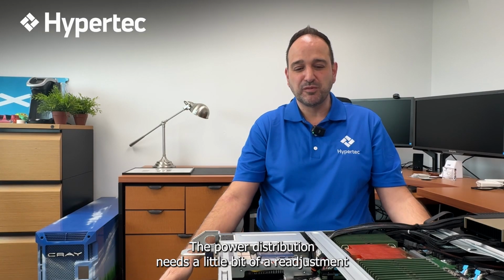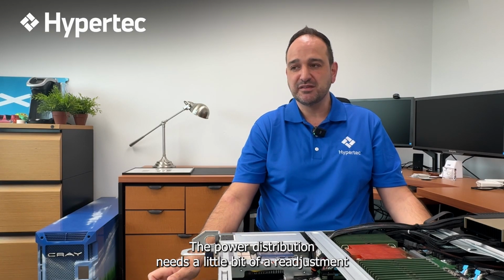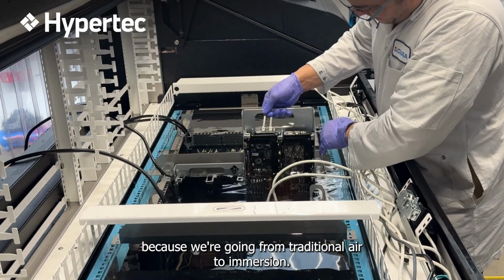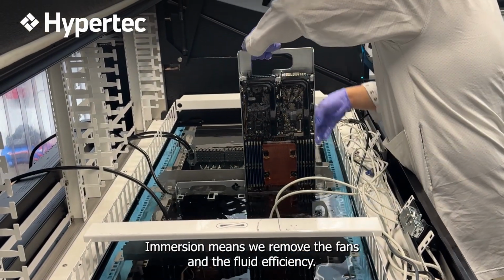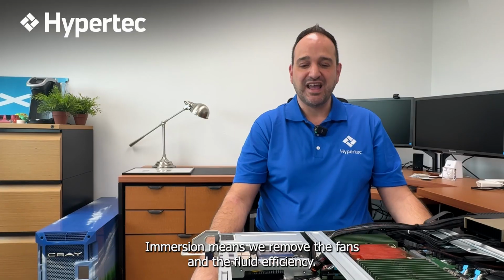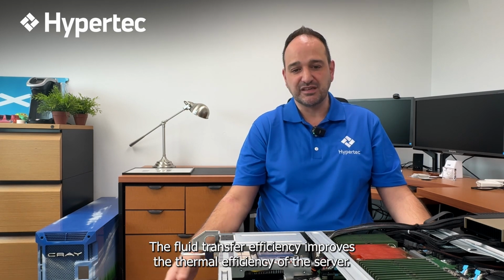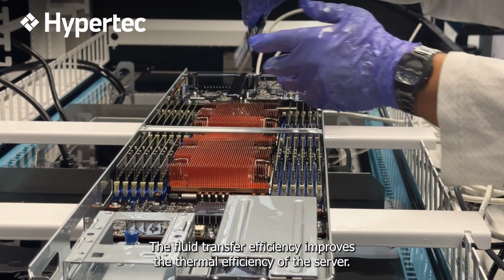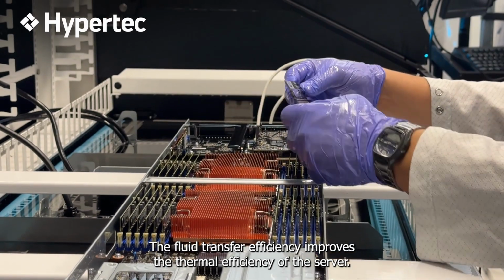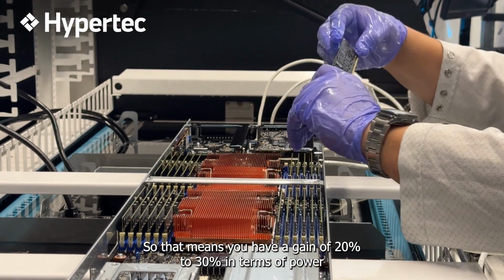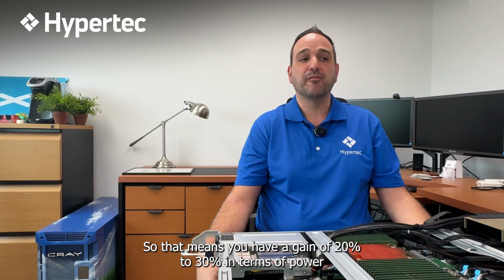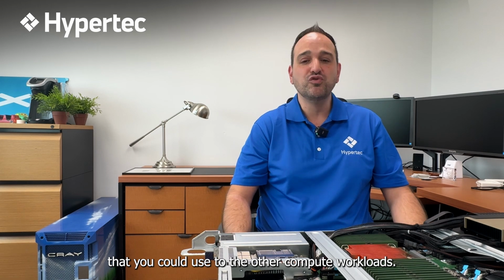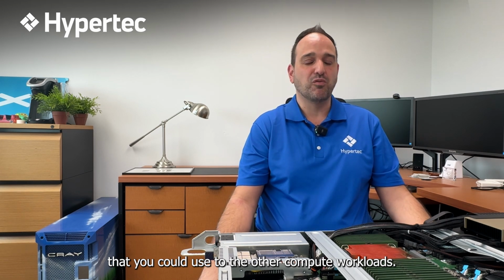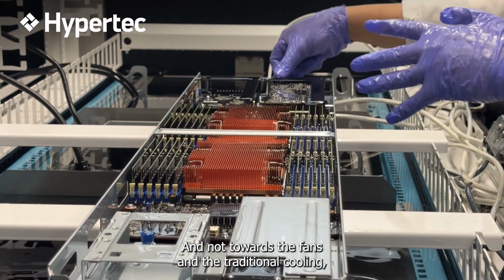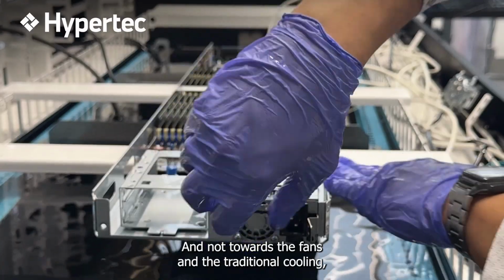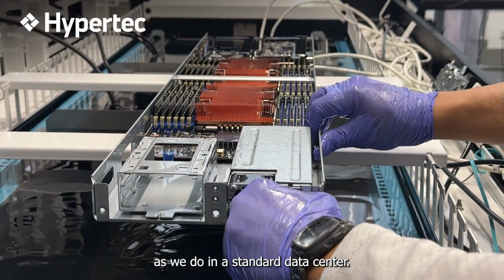The power distribution needs a little readjustment because we're going from traditional air to immersion. Immersion means we remove the fans, and the fluid transfer efficiency improves the thermal efficiency of the server. That means you have a gain of 20 to 30% in power that you could use for other compute workloads instead of for fans and traditional cooling as in a standard data center.